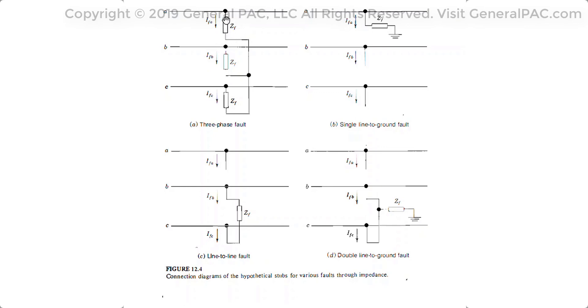And you may have this ZF, which is the fault impedance, which means it's an extra impedance that may be on the line or externally that contributes or reduces the fault current as a whole. So that's what ZF is, just this extra impedance that may be encountered with the fault. So a three phase fault perfectly balanced in terms of symmetric components. We only have the positive sequence component involved because it's a perfectly balanced fault. The negative and zero sequence components do not exist for a three phase fault. Perfectly balanced three phase fault.